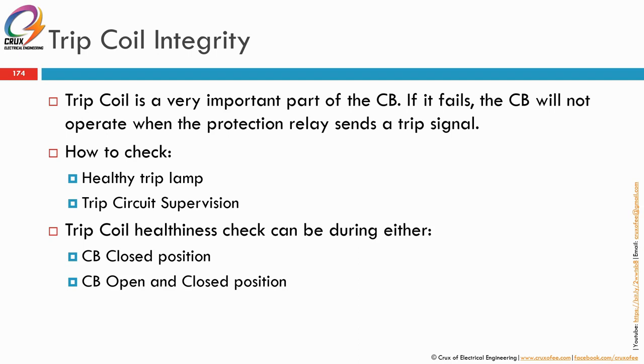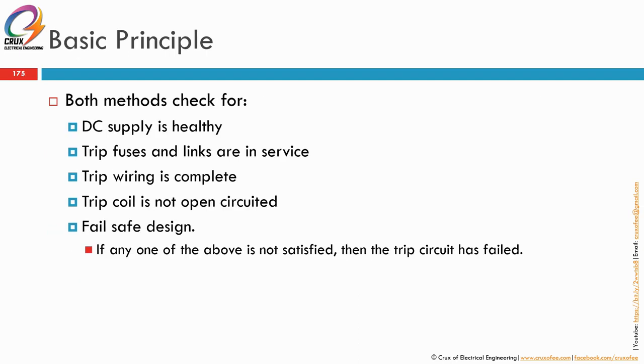Alright. So, what does the trip circuit supervision actually do? Both methods, the trip circuit healthy lamp check and the trip circuit supervision, actually monitor whether the DC supply or AC supply is healthy. The trip fuses and links are in service, meaning somebody did not leave the fuse in open condition after relay calibration. Maybe they forgot to put the fuse back in service.